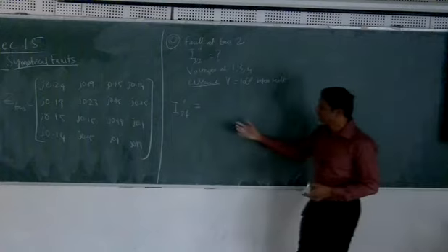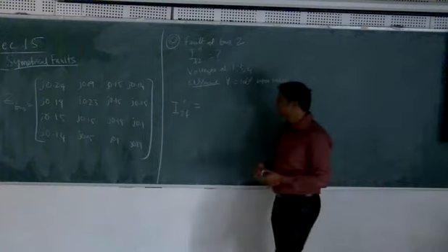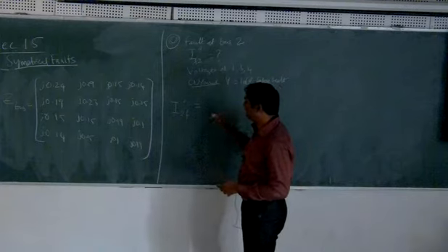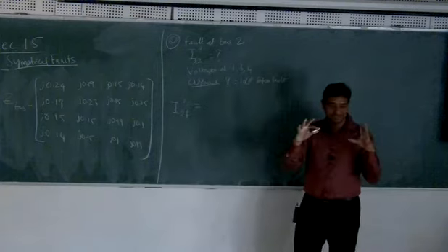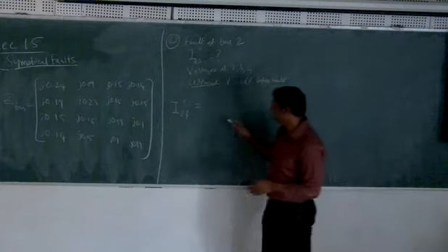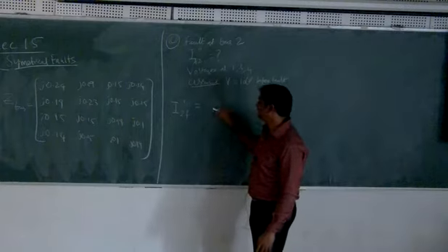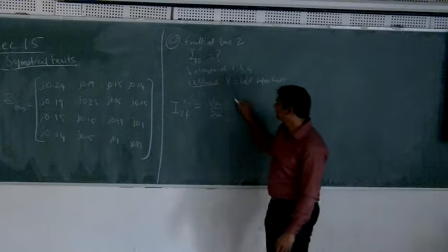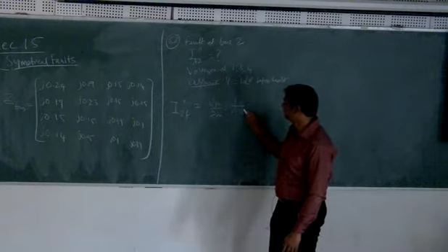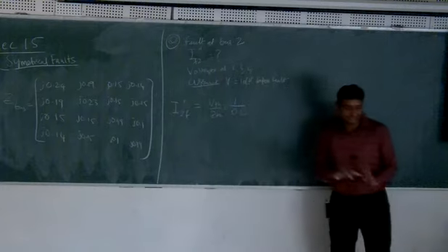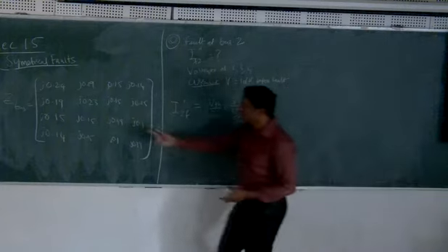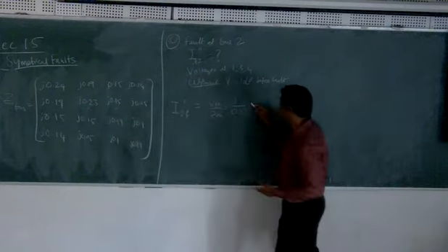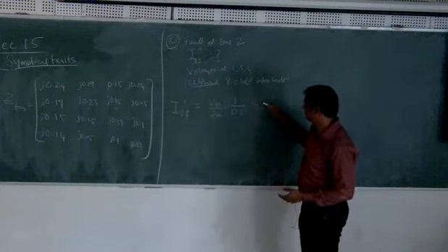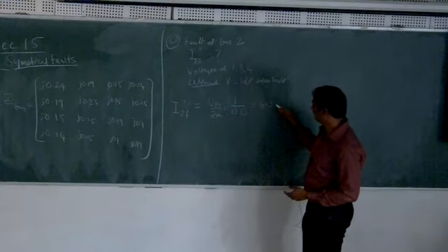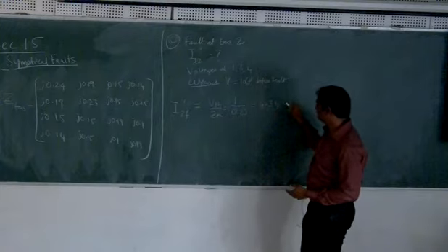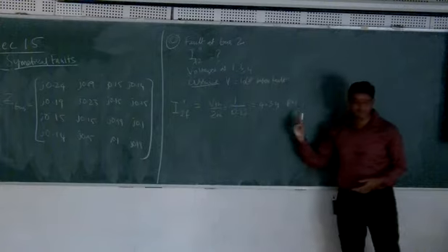How much should the fault current be? Just imagine there is a bus fault. Think of Thevenin's equivalent. So it is VTH by ZTH, which will be 1 divided by 0.23. I'm only interested in the magnitude because the impedances are all reactive. So 0.23 is coming from here. How much is this? 4.3. So now you can see it is about 4 per unit.